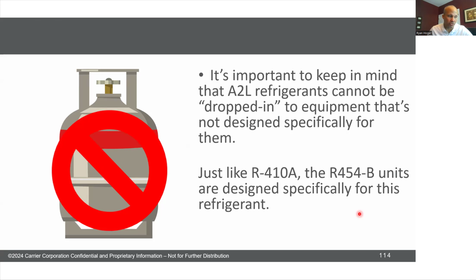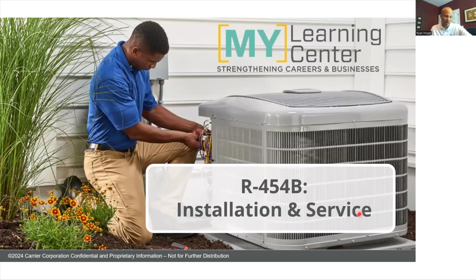Don't put the wrong refrigerant in the wrong machine. Whatever refrigerant it's specified for, use that refrigerant or another approved refrigerant. Like for example, if you have R-22 and MO99 is approved for it, you can put that in there, right? But 454B and R-32 are not approved to be put into any refrigerant systems that are not specifically those two things.